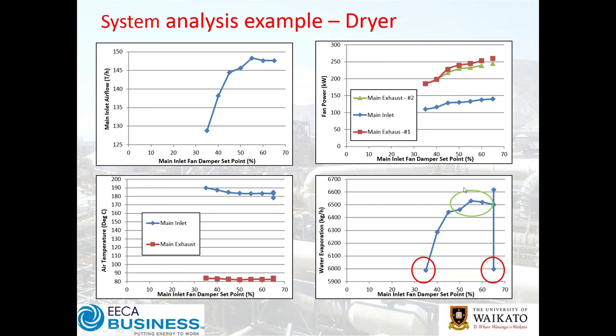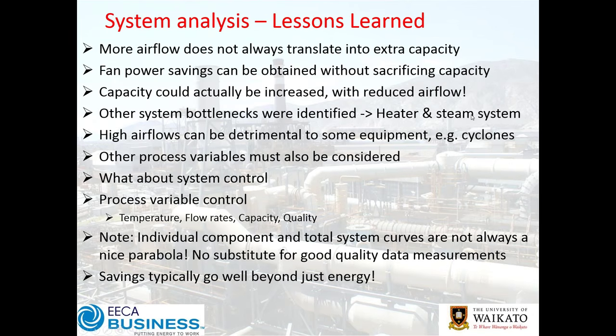There's a sweet spot where you want to run. The key take-home from this case study: don't automatically assume that more airflow is going to translate into extra capacity. Fan power savings can be attained without sacrificing capacity, and in this particular instance capacity was actually increased with reduced airflow and reduced energy input.